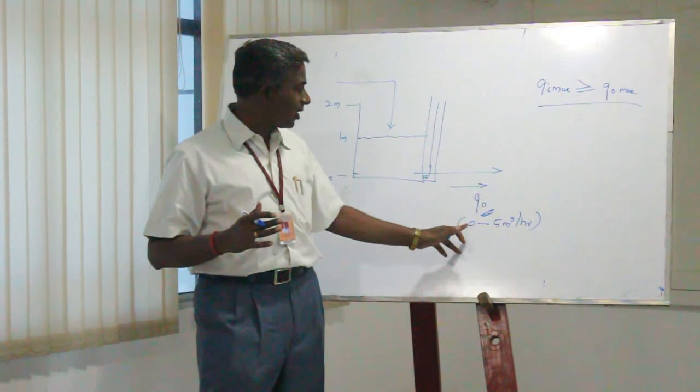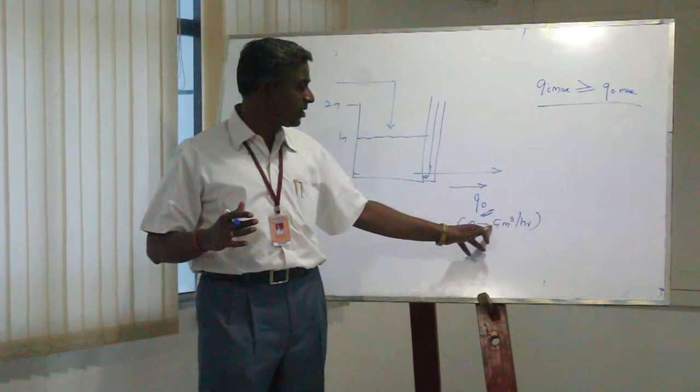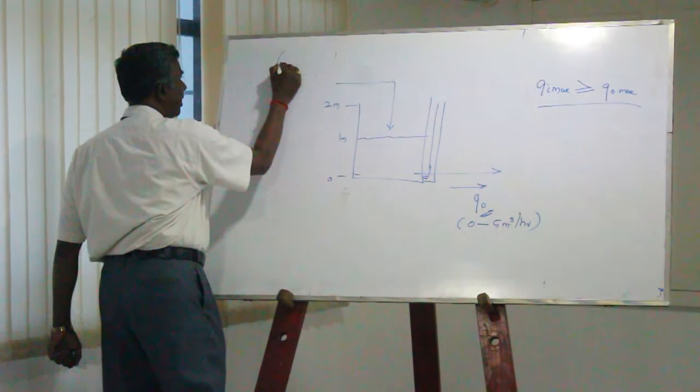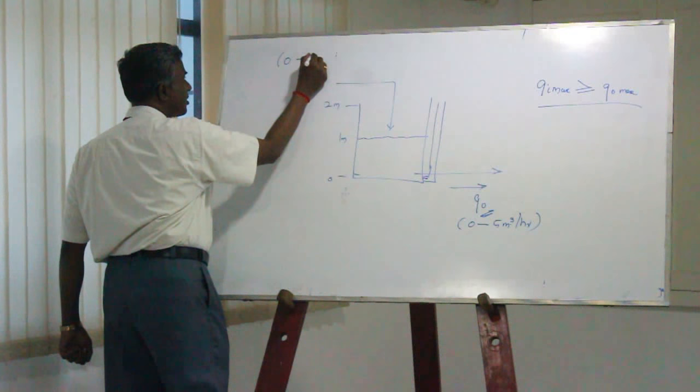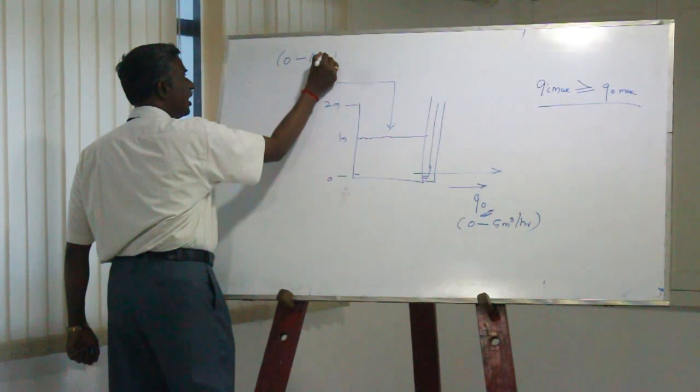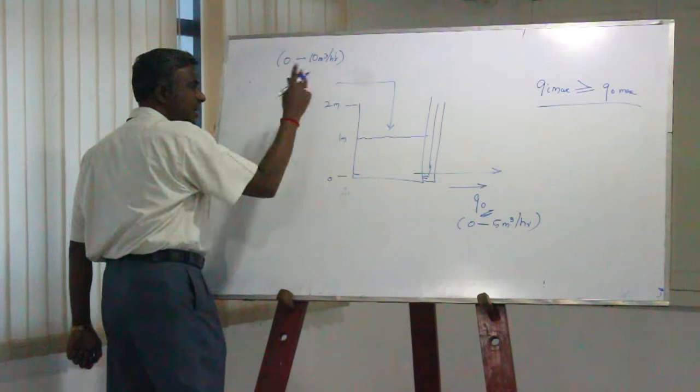If the vice versa happens, liquid is going to go through the tank and never get time to increase the level. To justify this, if Q0 is going to be 0 to 5 cubic meters per hour, obviously my inflow should have the capacity of at least 0 to more than 5. Here I assume it is going to be around 10 cubic meters per hour.